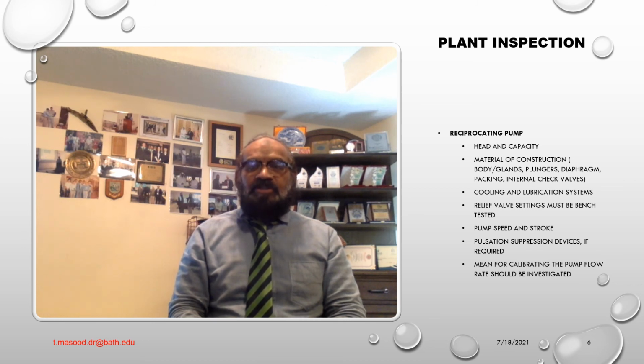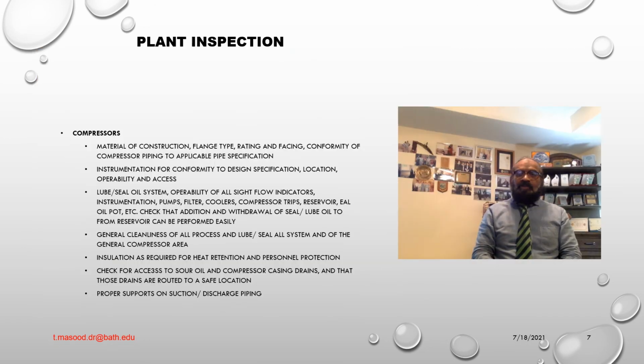Okay, next is the centrifugal compressor. Okay, centrifugal compressor. Following items should be checked in the field. Number one, material of construction, flange type rating, and facing conformity of a compressor applicable to pipe specification. Number two, instrumentation for conformity to design specification, location, operability. Number three, lube seal oil system operability of all sight flow indication instrumentation, pump, including auto start, filters, coolers, compressor trips, reservoirs, a seal oil pot, etc. That addition and withdrawal of seal lube oil to and from reservoir can be performed.